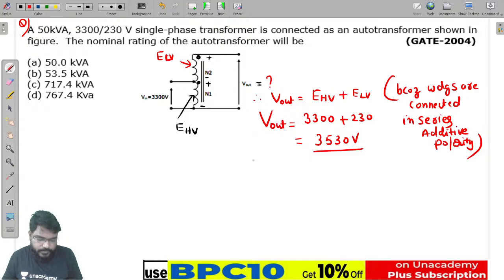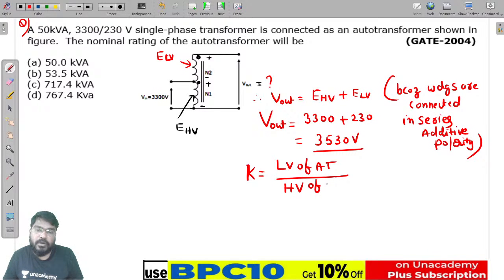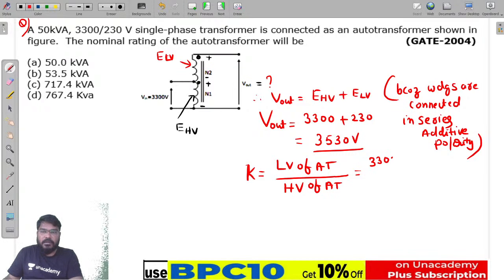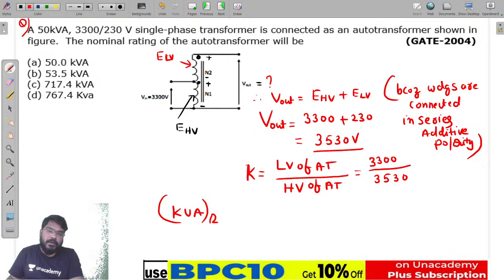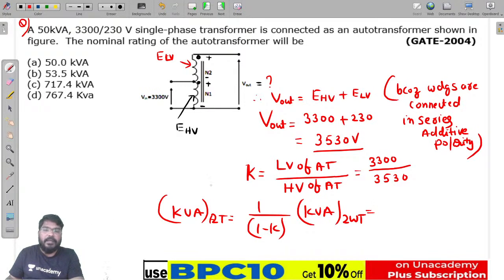Now let us find out K. How do we get K? K is always equal to the low voltage of the auto transformer divided by the high voltage of the auto transformer. Here this is the low voltage, and this is the high voltage of the auto transformer. So K is 3300 divided by 3530. The kVA rating of the auto transformer is equal to 1 by 1 minus K times the kVA rating of the two winding transformer.